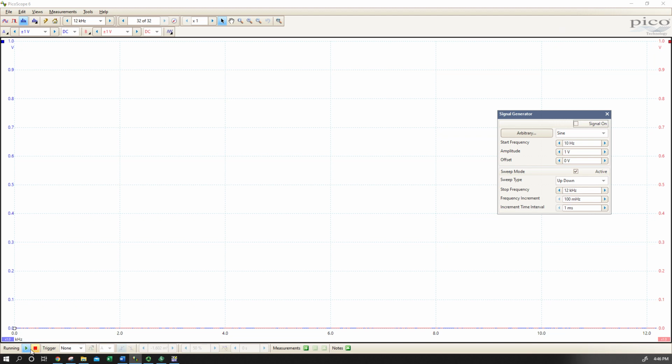So I am now collecting signal, and I'm going to sweep from 10 Hertz again, practically DC, to 12 kilohertz. And so we're going to turn our sweep on. So you can see our total circuit voltage signal, channel A, is up here, and here's our voltage drop over our load. They're equal scales actually, but we have it scaled such that we can see it climbing.